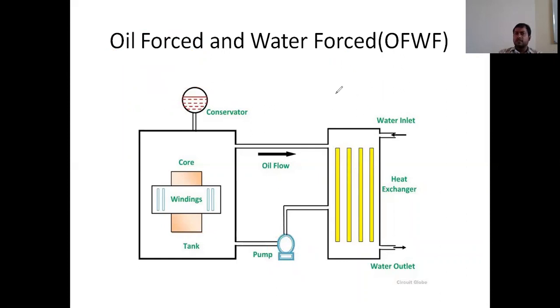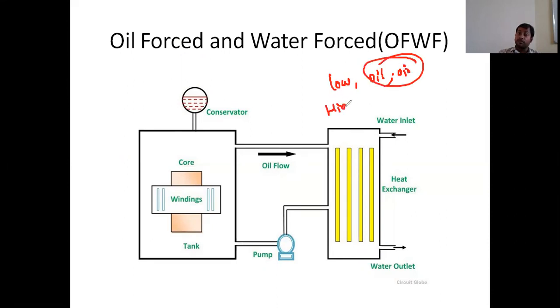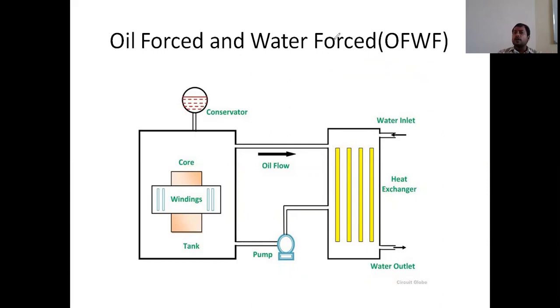These are the different types of cooling methods used in the transformer based on capacity. As capacity increases, we should use more sophisticated methods to reduce temperature. For low capacity, we use air natural and air forced. For higher capacity, we use oil natural and oil forced with air forced. For huge capacity, we use oil natural or oil forced with water forced — because water absorbs temperature much faster than air. This is all about the cooling techniques of the transformer.